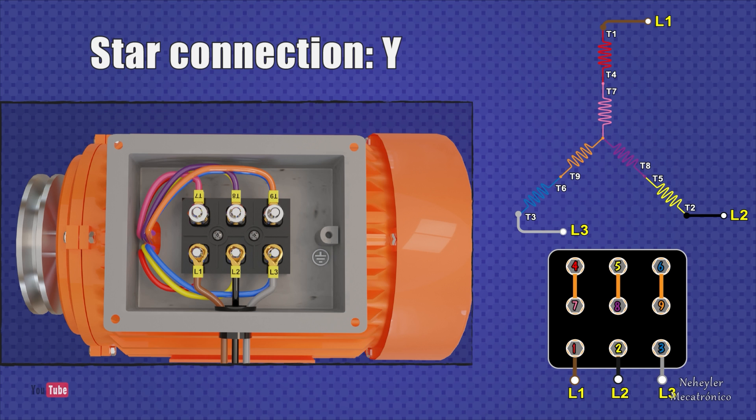Finally, the power terminals Line 1, Line 2, and Line 3 must be connected to Terminals 1, 2, and 3 respectively. The protective ground cable must also be considered, which must be connected to the metal part of the motor casing.